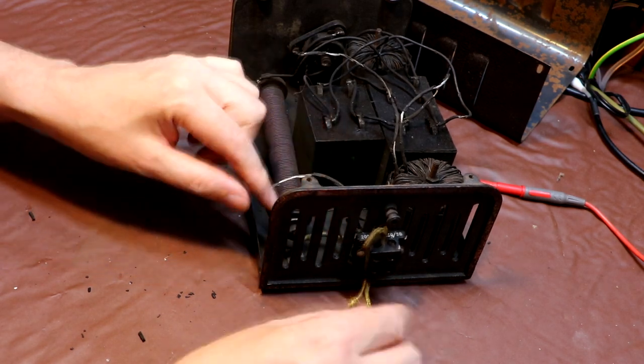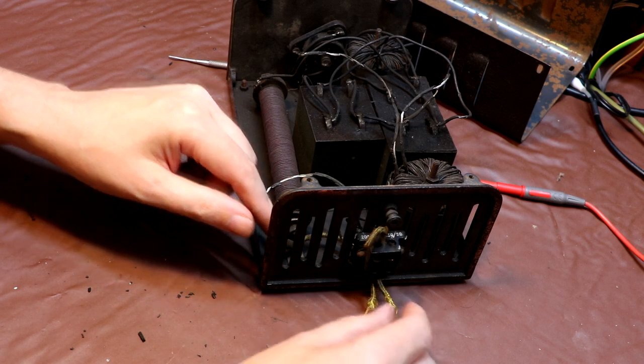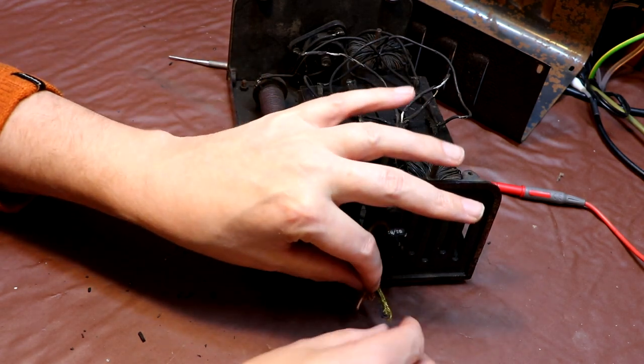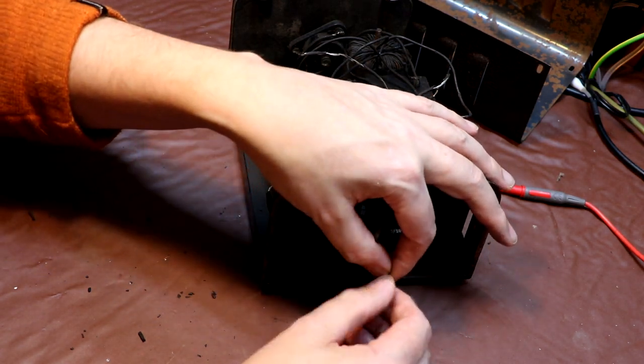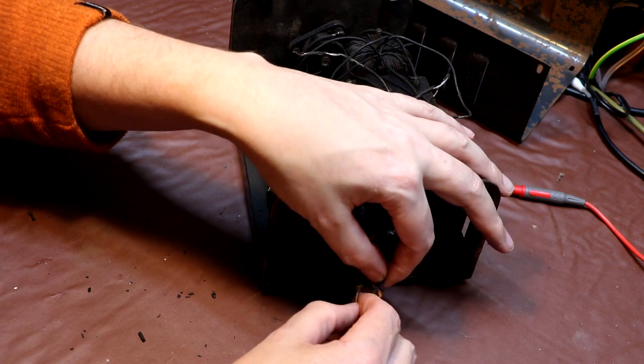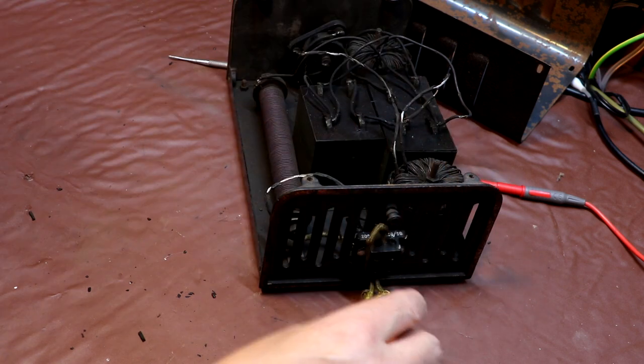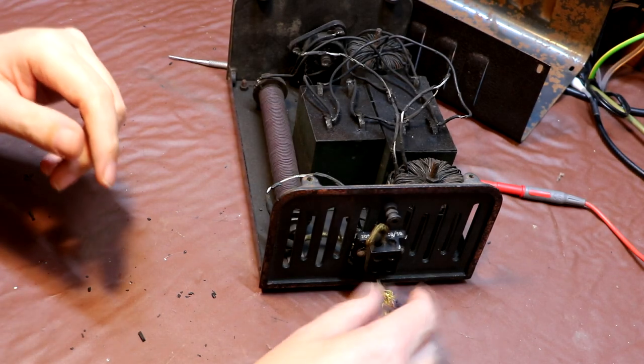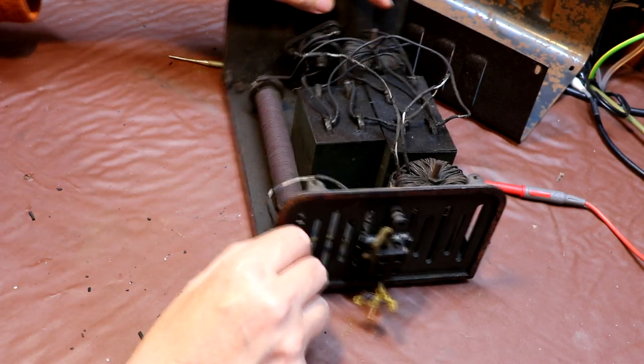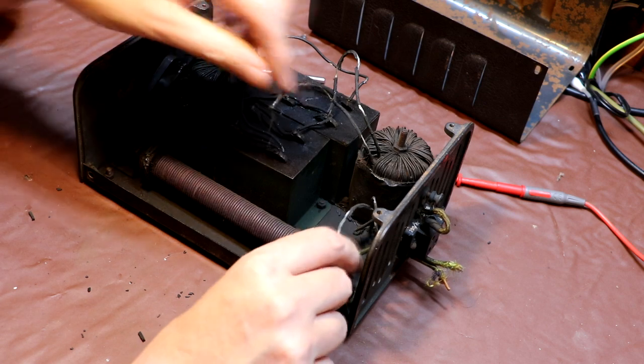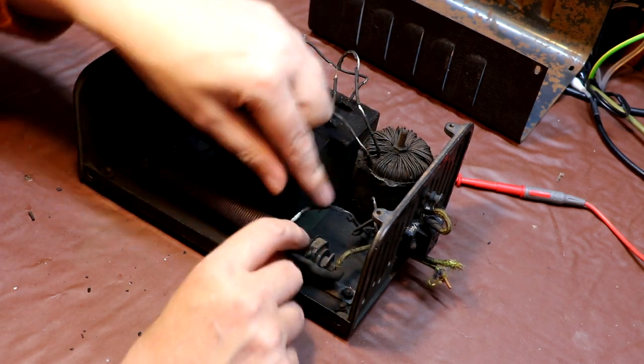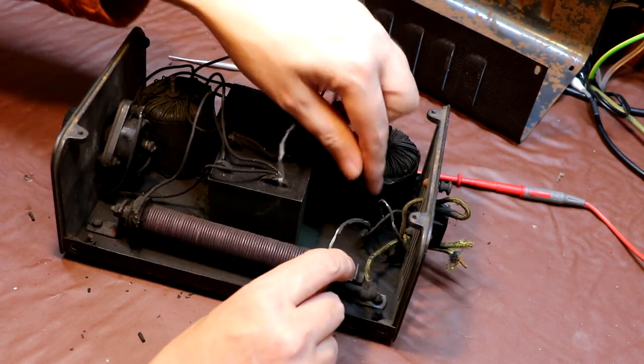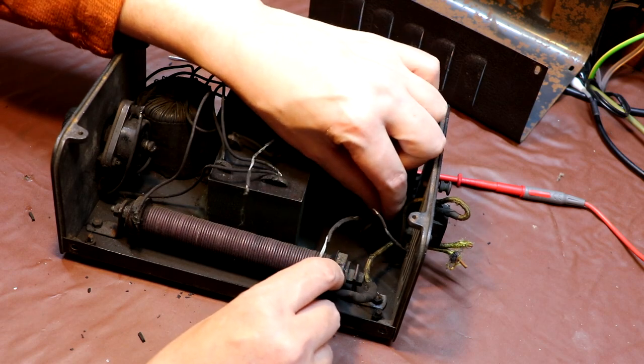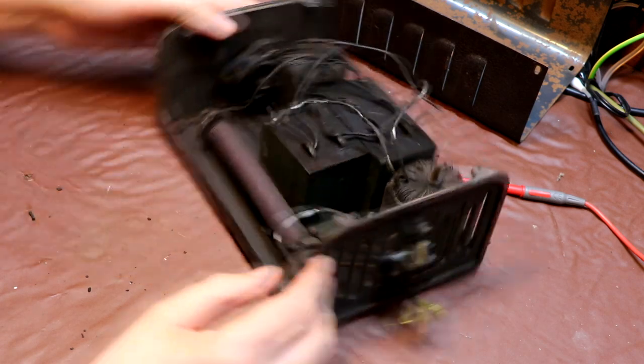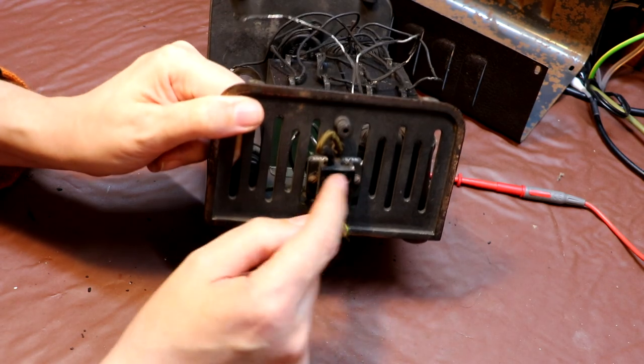Well, they've got knots tied in them, but what I think happens is, actually this is a more modern cable, because I can actually see that, oh maybe not, it's got brown conductors in it, but they look like plastic. So what we've got is the live and neutral coming into the transformer. One of the wires goes straight into the bottom of the transformer. But we've got two other windings coming out from the transformer, and they go to this contact block here.